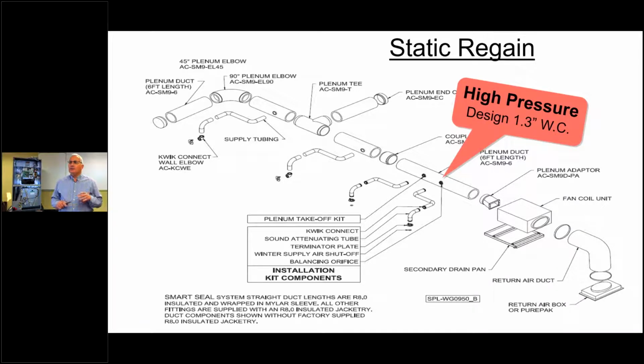And what I want to make sure everybody understands is we go out to a lot of older SpacePak jobs. And if you're seeing that the older plenum, which was maybe a fiberboard, and maybe it was round, and it's quite old, and if you touch it, it may feel a little spongy, or maybe it's breaking down, that whole plenum should be replaced. Don't just replace a section of it, replace the whole plenum. We've had a couple of jobs out there where they only did some piecework to it, and it never works out well. Replace the plenum. Today's is 9-inch round, it's spiral steel, and we have sealed gaskets. So when you put that together, it is a tight seal, it is not going to leak, and it's going to tremendously change how the system performs, okay? So that's what we want to call out here.